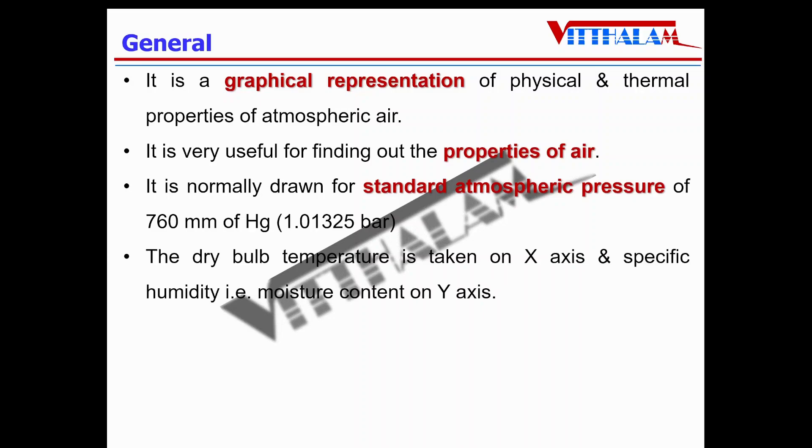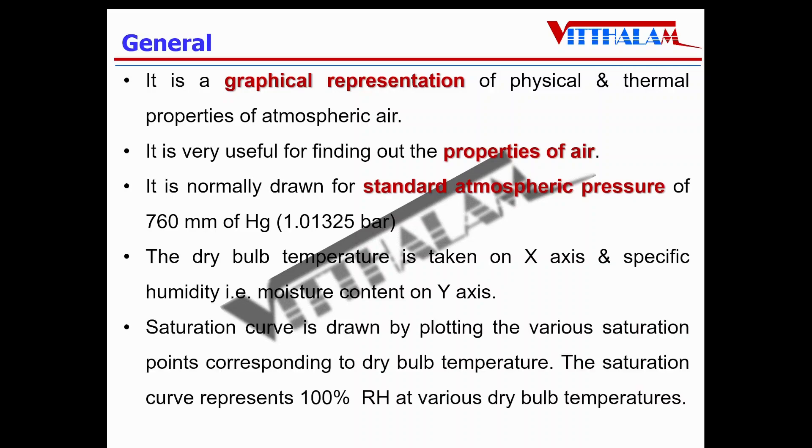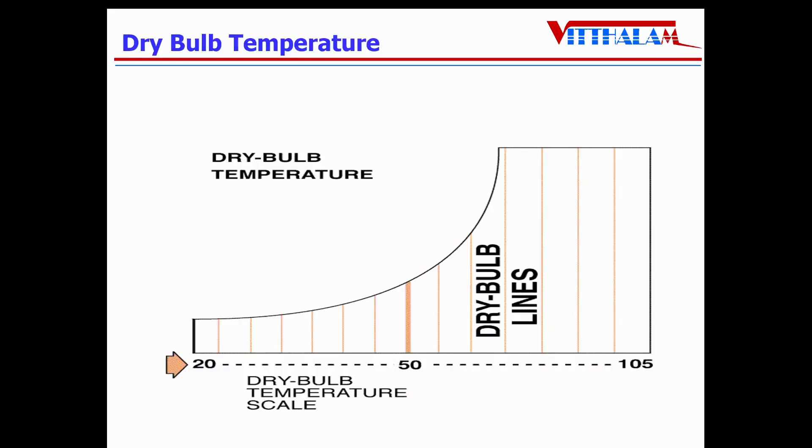Boundaries of the psychrometric chart are dry bulb temperature on the x-axis, specific humidity that is moisture content on the y-axis, while the saturation curve that is 100% RH is drawn by plotting the various saturation points corresponding to dry bulb temperatures. This saturation curve is an upper boundary representing saturated air or 100% moisture holding capacity at various dry bulb temperatures. The curve looks like this - dry bulb temperature is on x-axis while specific humidity that is moisture content is on y-axis.